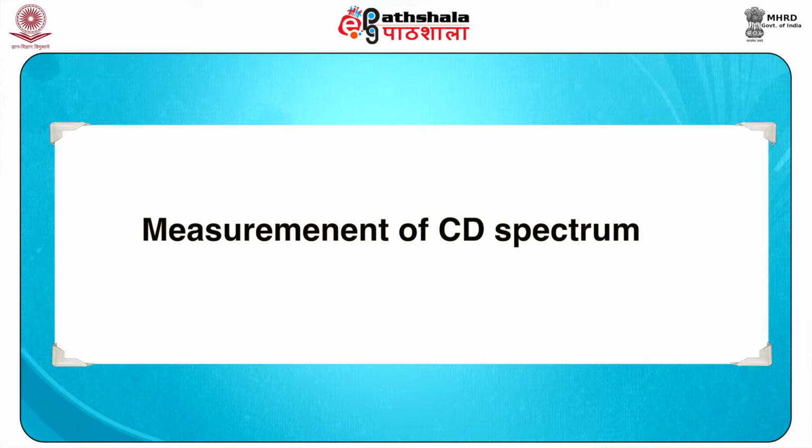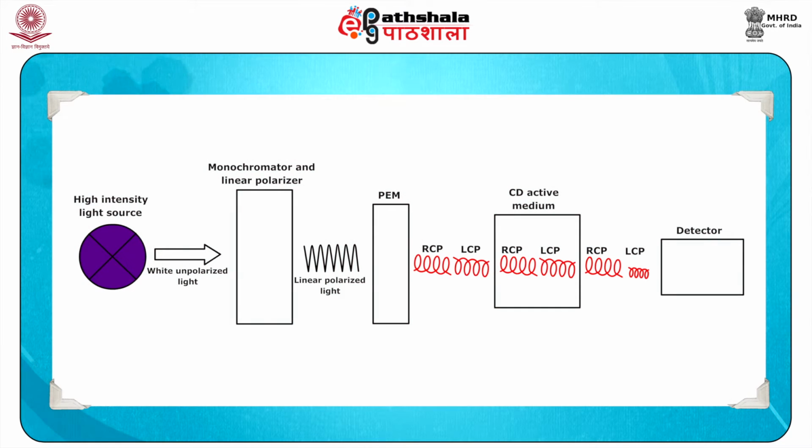How is a CD spectrum measured? Described in the figure is a CD instrument. Here light goes through a monochromator and then you can see through a sample wherein a CD spectrum is derived and then detected. Most commercial CD instruments are based on the modulation techniques introduced by Grosjean and Legrand.